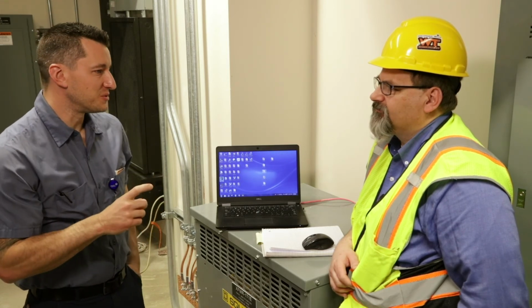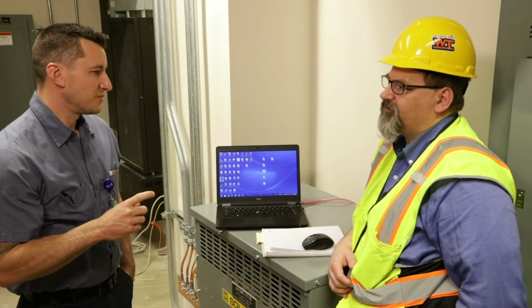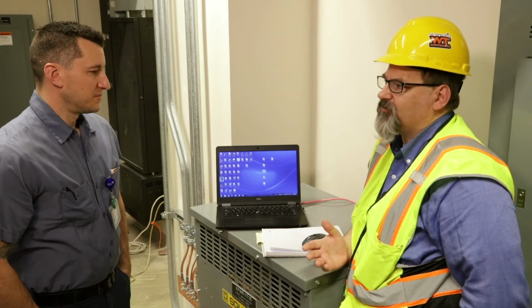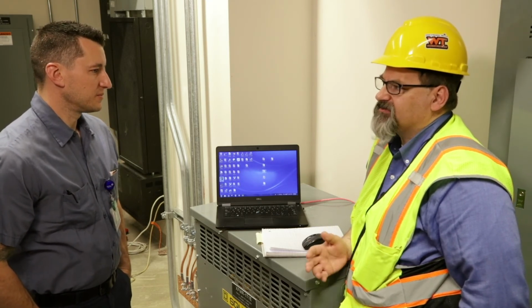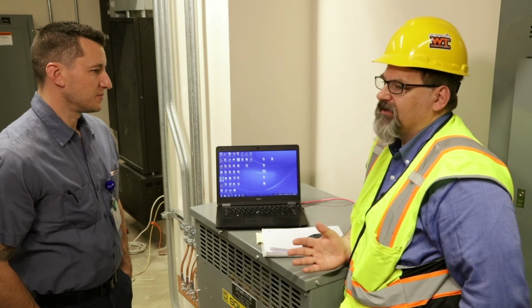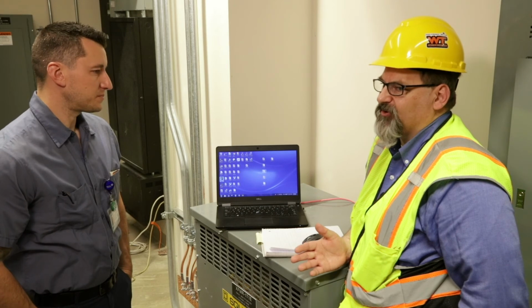So you just brought up a good question. I was thinking about those blue receptacles that are in the room, those are being fed off plug load controllers, yeah, LMPL 101s. Those are only out of the box, right? They're programmed to listen to occupancy. And all the occupancy sensors out of the box, they reset and they control. That's normally not something that we program. In certain cases, in this building, we programmed it.